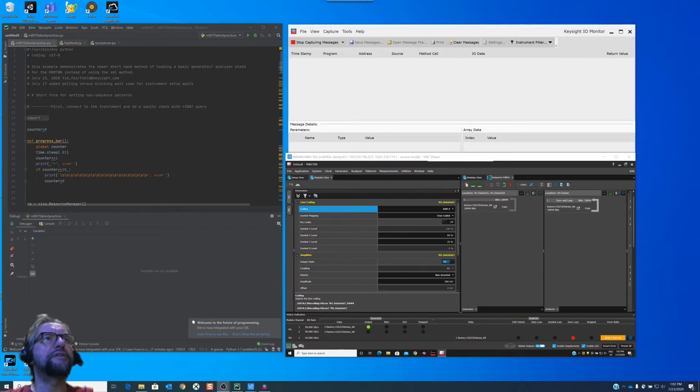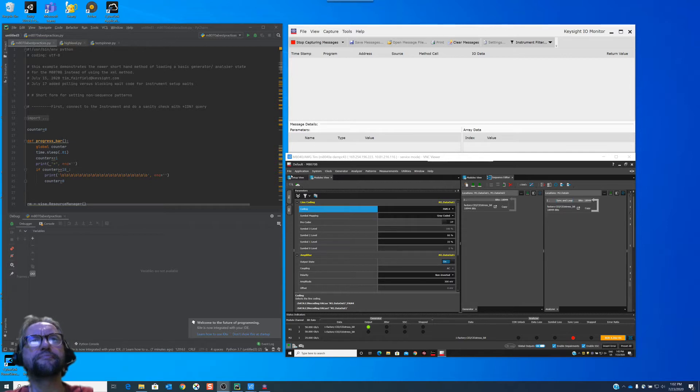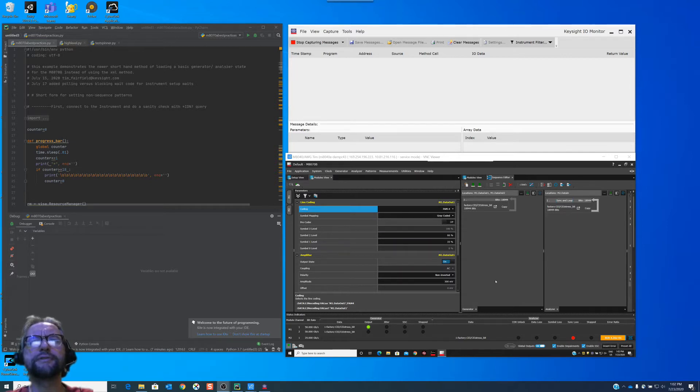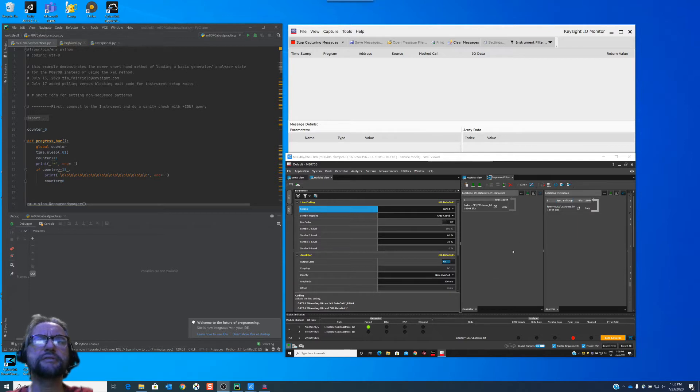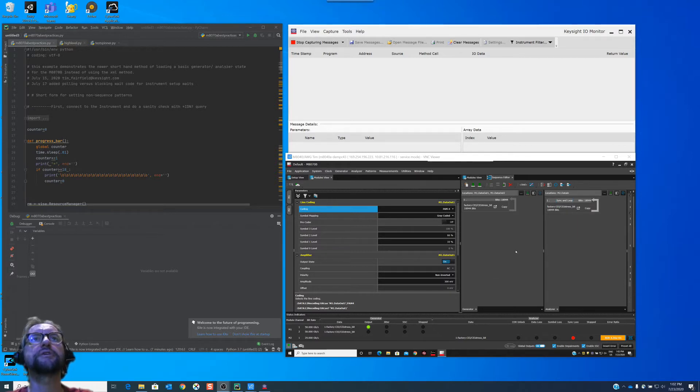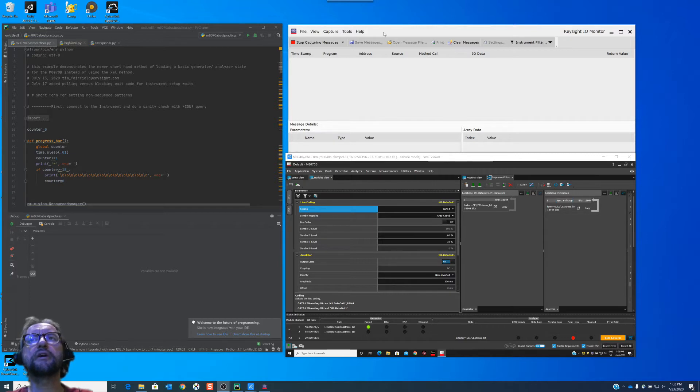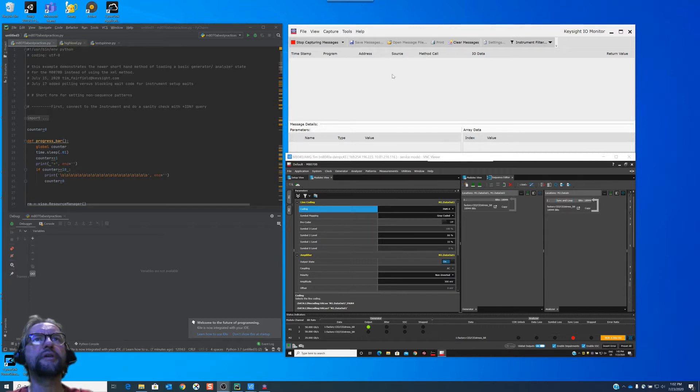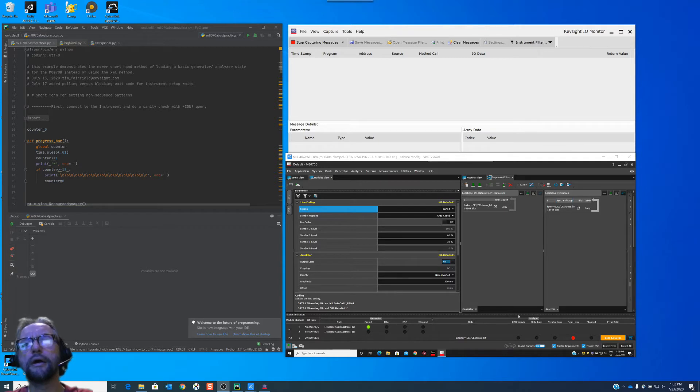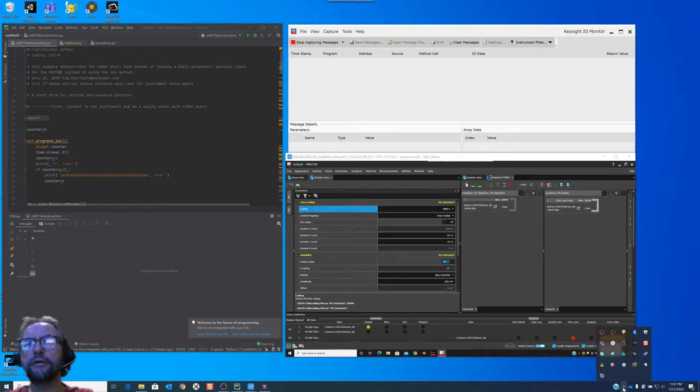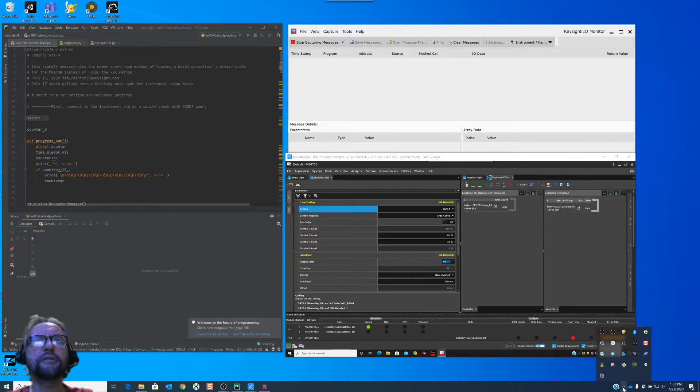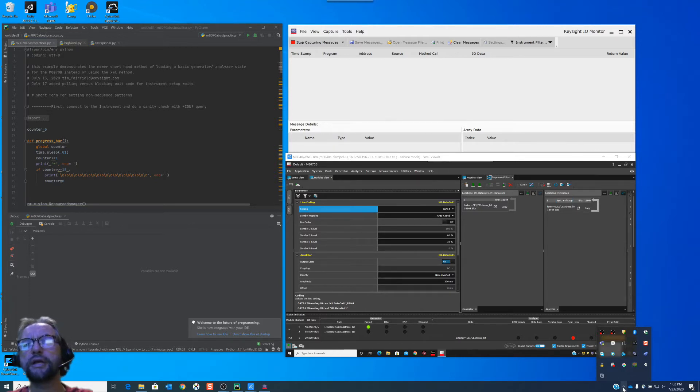On the upper left here, I've got my Python environment. I'm using PyCharm for this. On the bottom right is the actual software that runs on the M8070B. This is the controller software that would control the BERT that we just saw. And at the top, I'm using IOMonitor to monitor the traffic from the Python program going in. If you aren't aware of this, it's very useful for debugging, looking to see that your commands went through, what did get formulated when it came through.